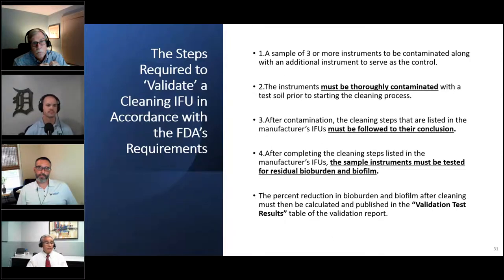A minimum sample of three must be selected, and you need to contaminate three additional instruments to serve as a control. The instrument must be thoroughly contaminated with the test soil. After contamination, the cleaning steps listed in the manufacturer's IFU must be followed to their conclusion. After completing those cleaning steps, the sample instrument must be tested for residual bioburden and biofilm.